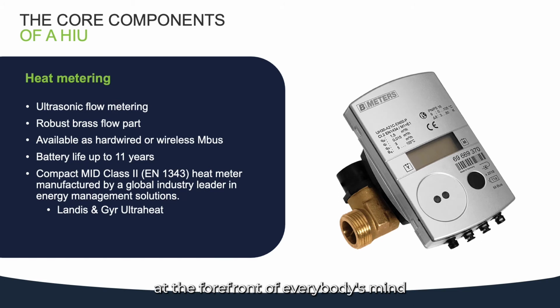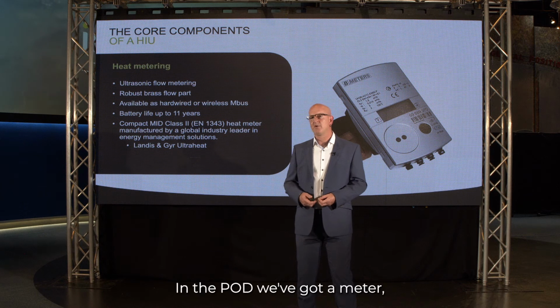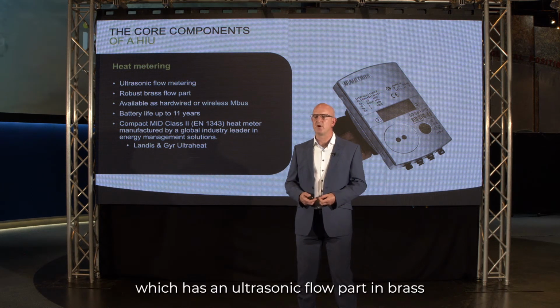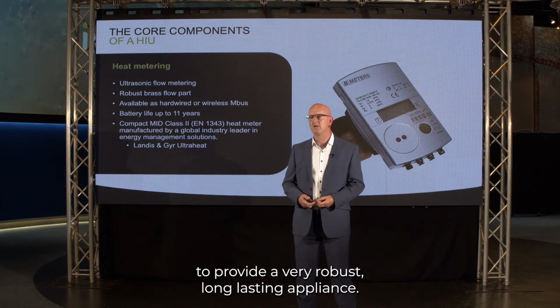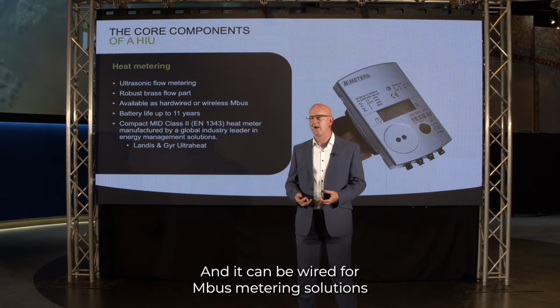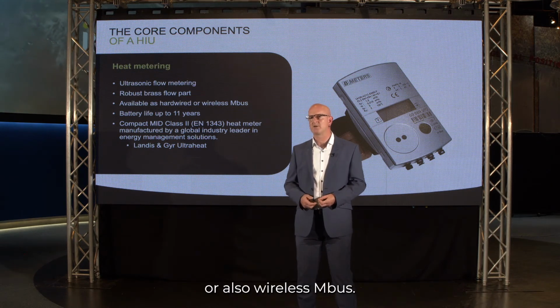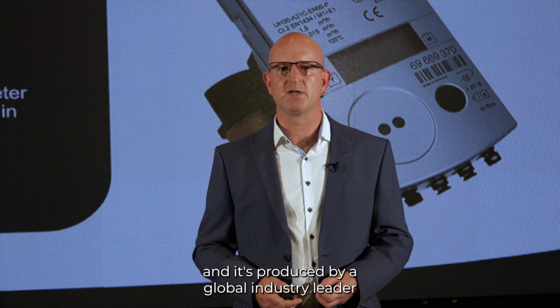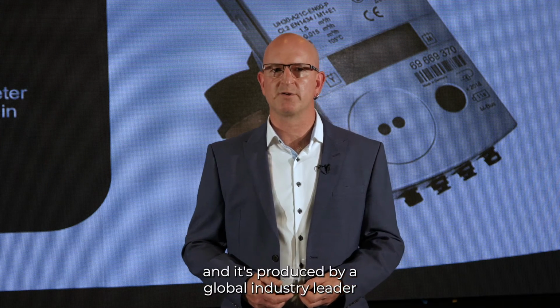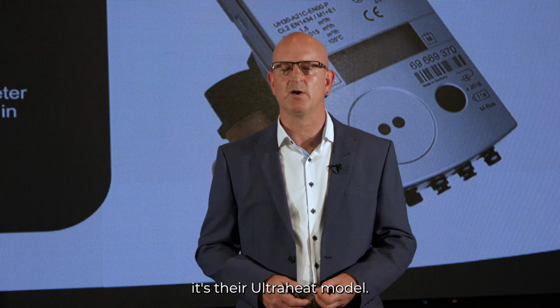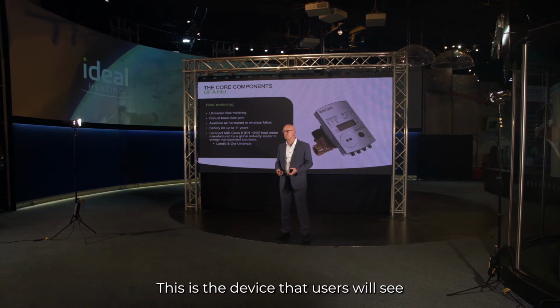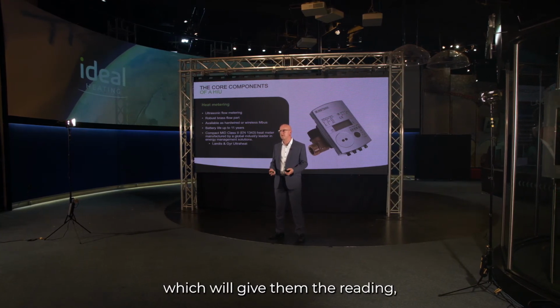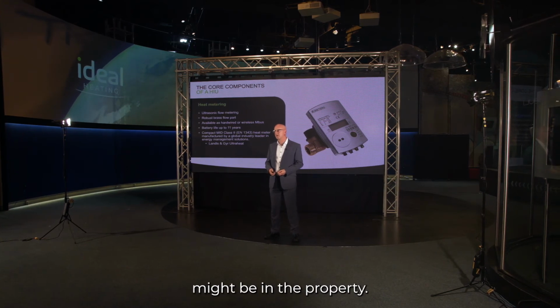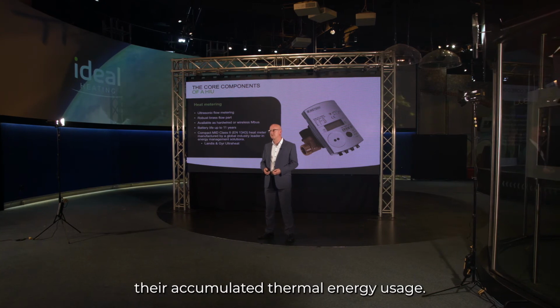Obviously, energy usage is something at the forefront of everybody's mind, and efficient use of energy. And in order to monitor the energy used by your heat interface unit, you have to provide a heat meter. In the pod, we've got a meter which has an ultrasonic flow part in brass to provide a very robust and long-lasting appliance, and it can be wired for M-Bus metering solutions or also wireless M-Bus. The battery life is up to 11 years, and it's produced by a global industry leader in energy management solutions, Landis+Gyr. It's their Ultra Heat model. This is the device that users will see on their heat interface unit, which will give them the reading much the same as the gas or electricity meter might do in the property. This meter tells them their accumulated thermal energy usage.